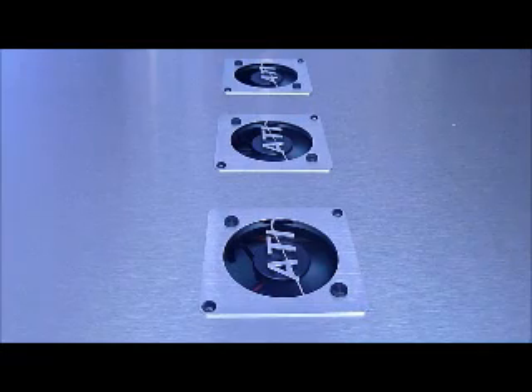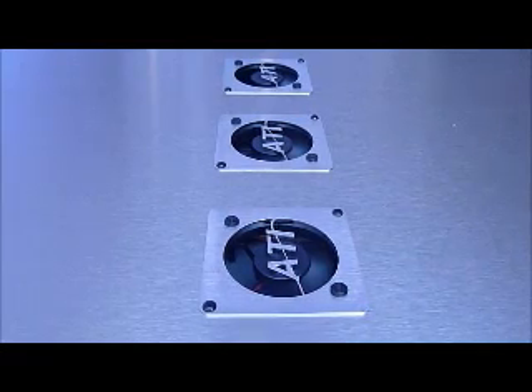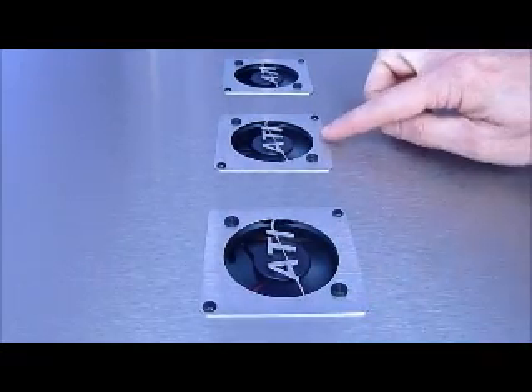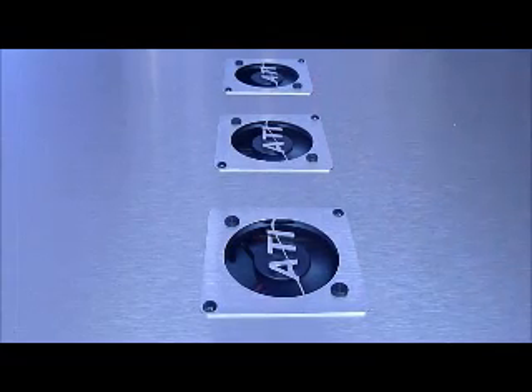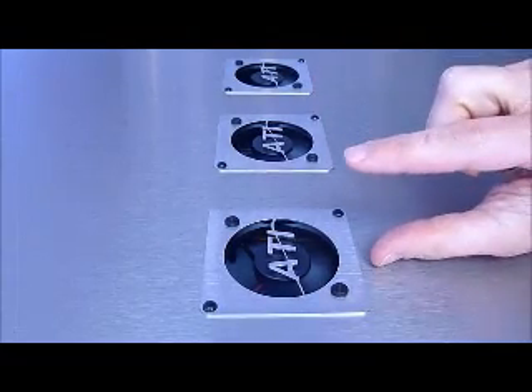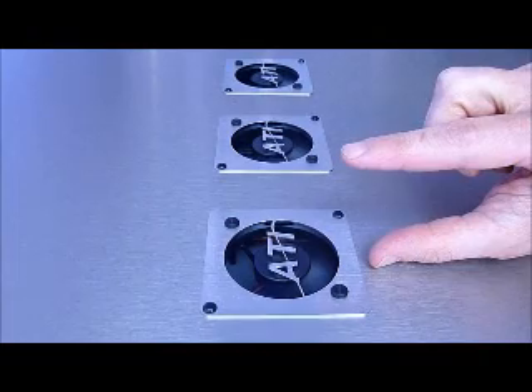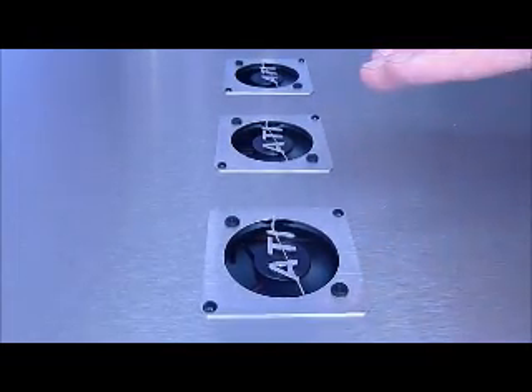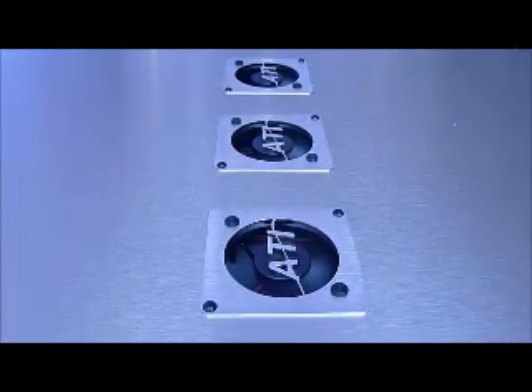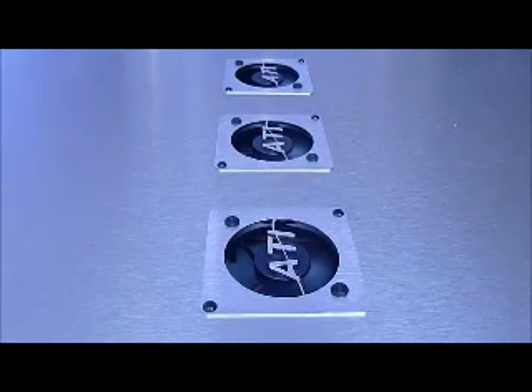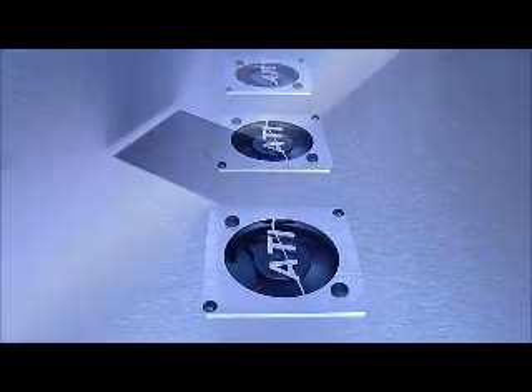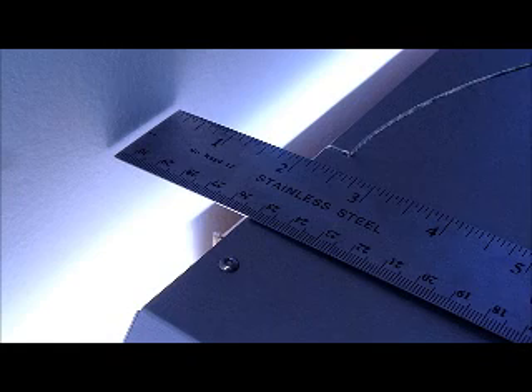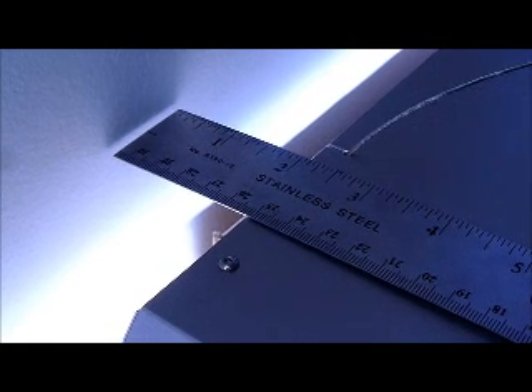The first thing you want to check is to make sure that all the fans on your fixture are spinning. The second thing would be to make sure that you've got at least a 2 to 3 inch clearance between the top of the fixture itself and whatever is above the fixture. If there is not clearance there, the fans can't draw in cool, clean air, and the fixture will not cool effectively.